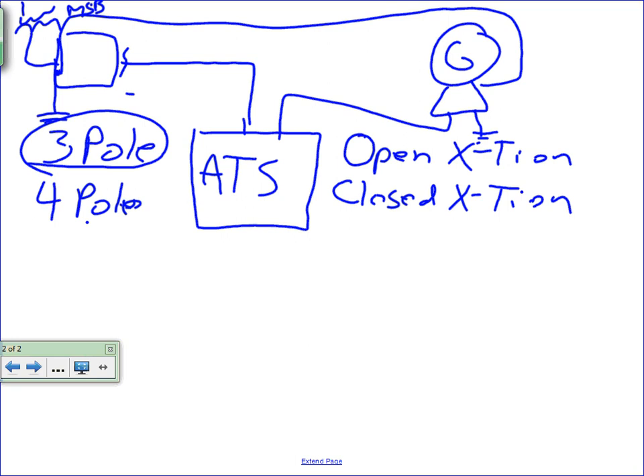In your other example, where we were feeding right from the utility to the transfer switch, not only do you need a 4-pole, but then you also need a service entrance rated transfer switch. So basically built into that transfer switch is going to be overcurrent protection, a breaker or a switch or something. Normally a breaker, upstream, internal. Can't even write. Anyway, so now that utility service will be bonded inside this enclosure, right? Yes. Yeah.